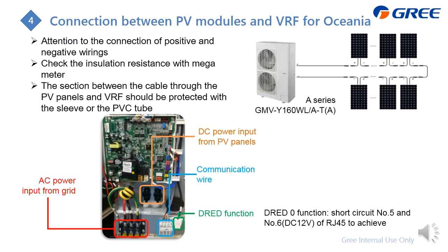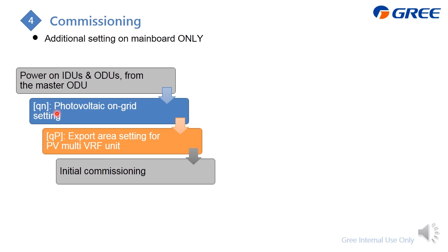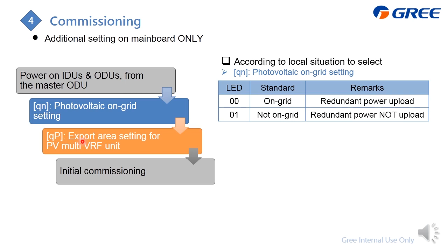Here are the steps. Just power on the indoor unit and outdoor unit. The first thing you need to do is select the QN, which is for the photovoltaic on-grid setting, which is this one. You need to set this one. This is to choose whether you would like to upload or not upload to the grid power. And after this is to set the QP for the export area, and we have options for Australia or for New Zealand. And after that is to initiate the commissioning. After it, it is completely the same as the regular GMV.